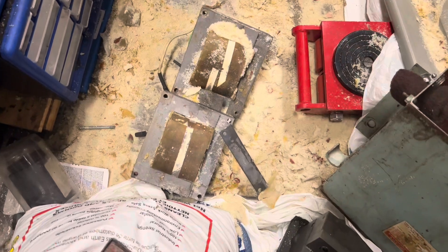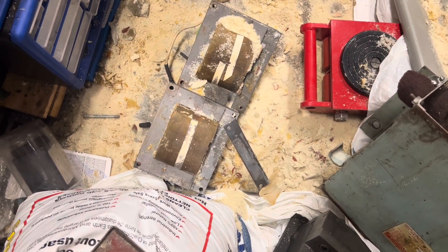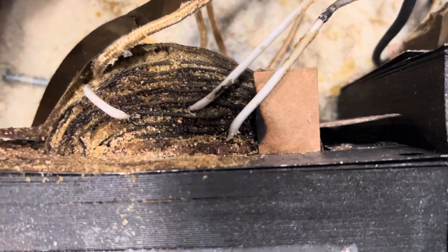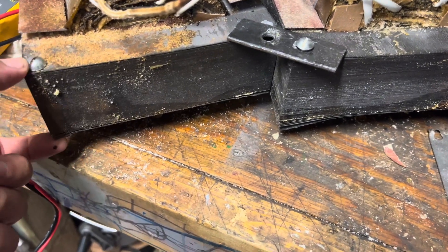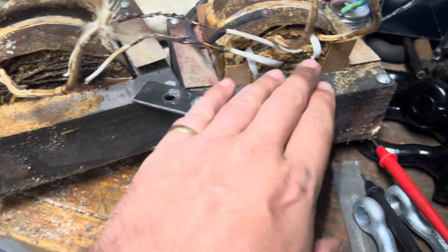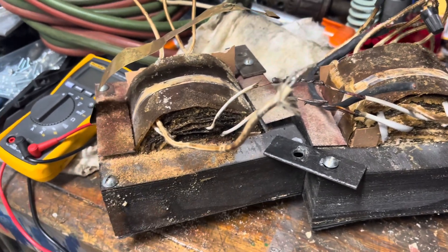It is free. We're not in the greatest configuration, but we can flip them over and start the next phase. Sadly, there's our failure. For completeness I'm going to measure the thickness and take the pieces off one side. I won't touch this coil because it doesn't look like it has a fault — we'll go through and see if there's anything bad in the other one.